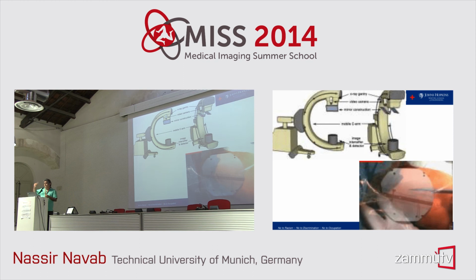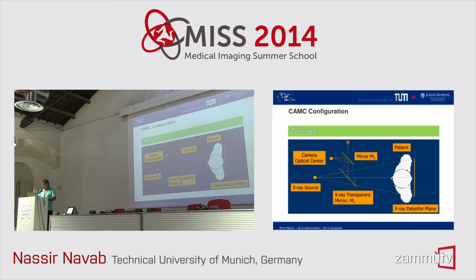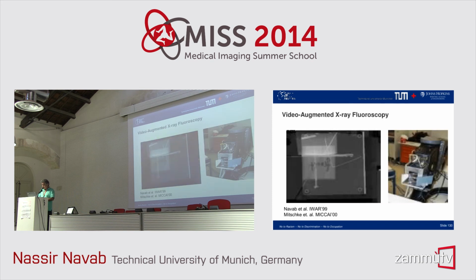In the middle of that, I went to a mixed reality conference in Japan, where we were doing industrial augmented reality. I saw a bunch of HMDs from Sony, and all of them had a camera and a prism, like Google Glass, to align the eye of the user, the camera and the display. On the airplane flying back to Erlangen, I thought: if I replace the eye of the user with X-ray, then I can do exactly the same thing. So we arrived there. This was the first drawing or concept.